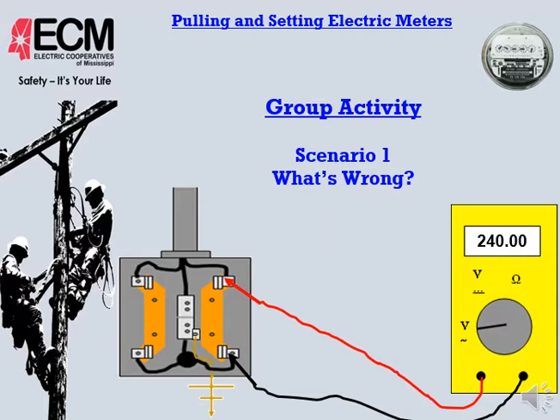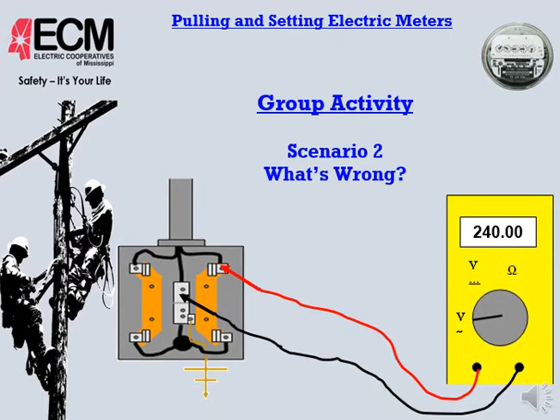But again, the main thing we're trying to get across here is that when you get voltage in a position where you shouldn't, we hit our brakes. We don't set the meter. Now this one here happens quite a bit. Scenario 2. We get to this point, phase to ground on our source side, and we get 240 volts.